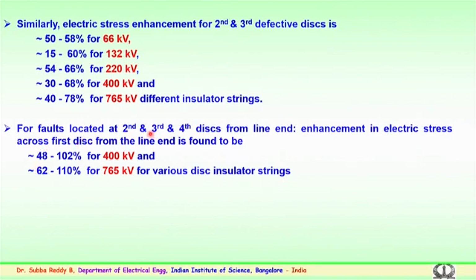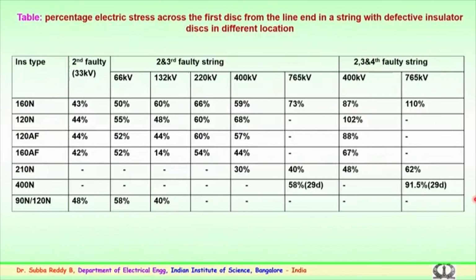So, what happens in the case of faults where 3 insulators are shorted or faulty in the string from the line end? You can see the increase will be more than 100% for 400 kV and 765 kV disc insulators. So, this table gives the entire information about the percentage of electric stress across the first disc. Here the first disc is assumed to be a good one, the second, third and fourth are treated as faulty, and simulations have been conducted and stress calculations made for various discs. You can see from 160 kilonewton to 210 kilonewton, 400 kilonewton.